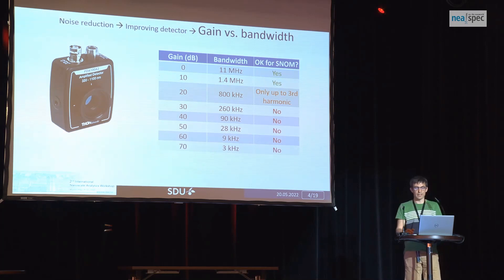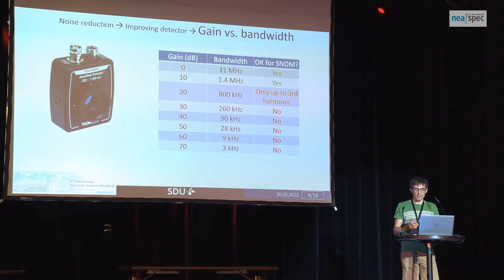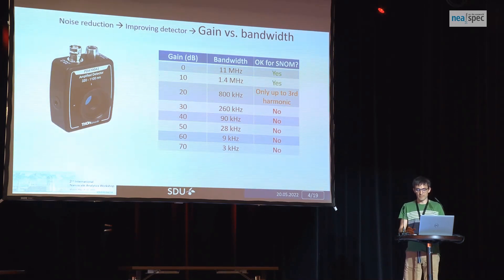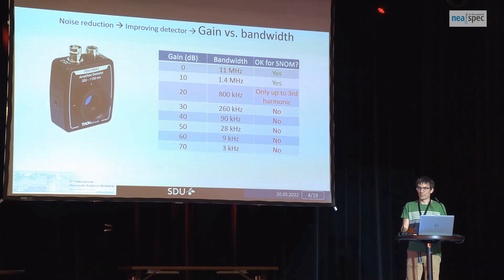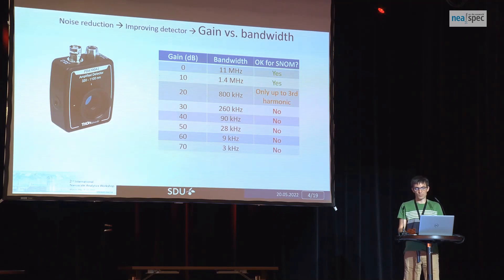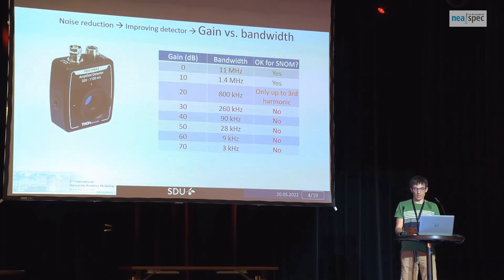Another important parameter of the detector is bandwidth. Sometimes the source is very weak and you need to amplify the signal, but for the price of amplification you pay with bandwidth. Remember that in the Neospec system you demodulate at high harmonics — preferably at the third and fourth harmonic — and therefore you should pay attention to the detector bandwidth. For fourth harmonic detection it should be above 1 MHz. Therefore, you cannot use just any amplification; only a small range of amplification is usable.